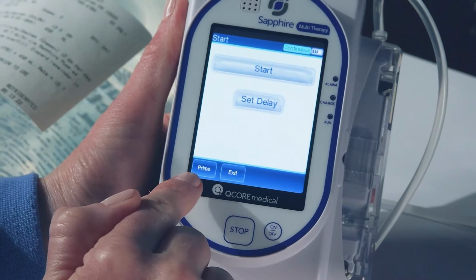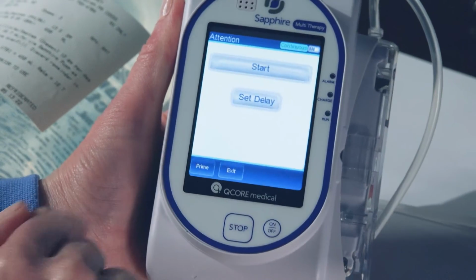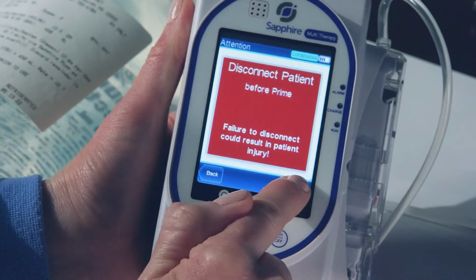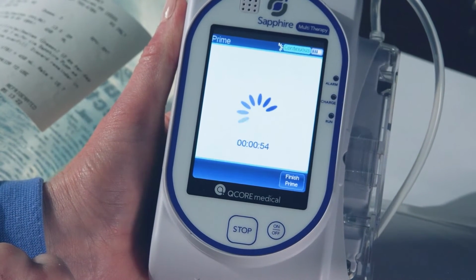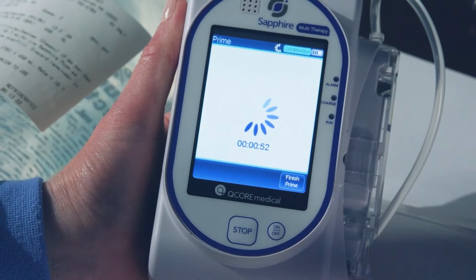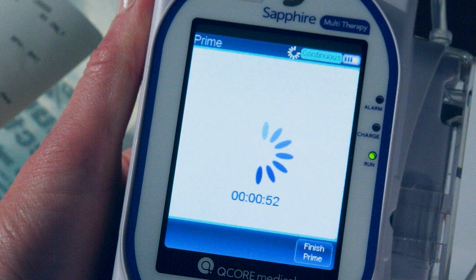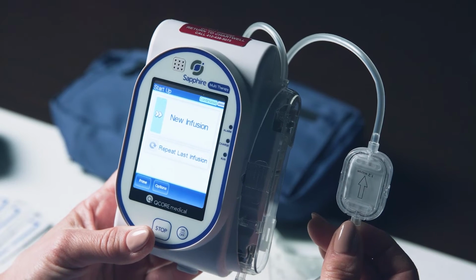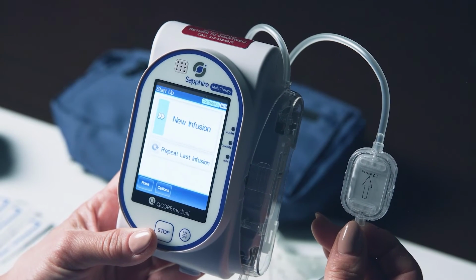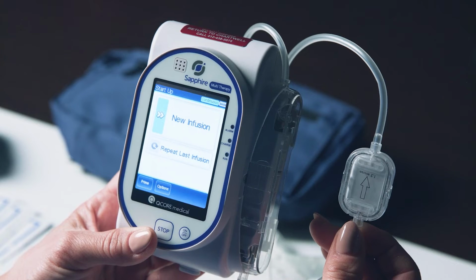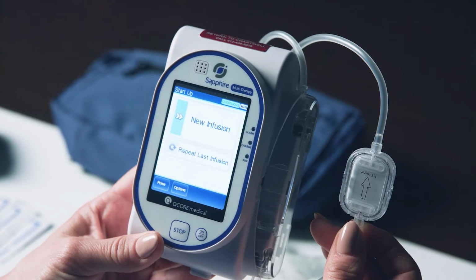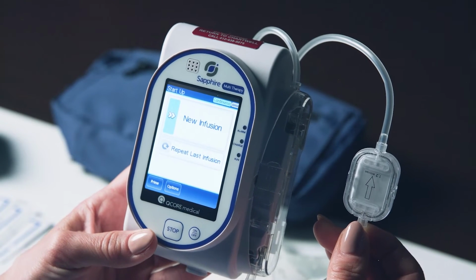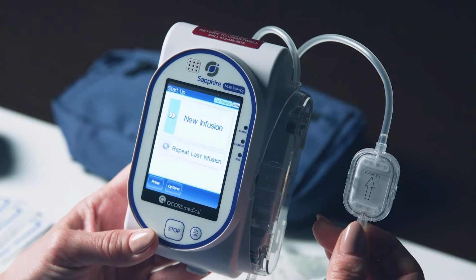The pump will alert you to disconnect the tubing from the patient. Press Prime because you have not yet connected the tubing to your IV catheter. Then, the pump will begin priming the tubing. If your tubing includes an inline filter like the one shown, you will need to hold the filter with the arrow pointing up to allow the fluid to fill the chamber and force the air out.